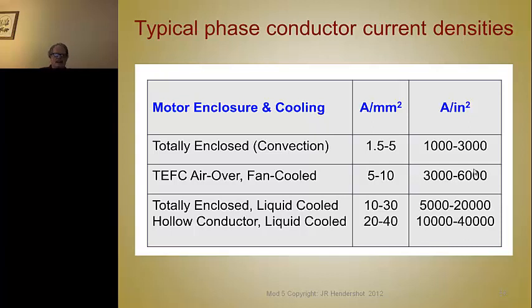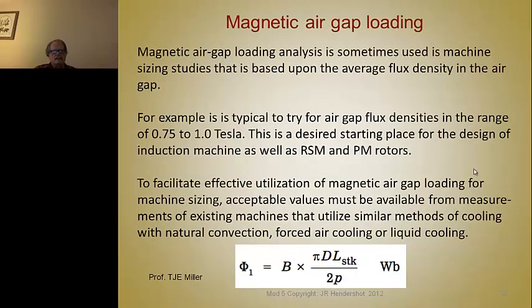If you go much over 5 amps per square millimeter, you need more serious cooling. For magnetic air gap loading, you want to try to have an air gap flux density in the range of 0.75 to 1 Tesla. In a former lecture we assumed that an induction motor is between 0.65 and 0.85, so this is all in the same range. You want to strive for as high as you can — it's pretty tough to get more than 1 Tesla. This is a desired starting point for induction machines as well as reluctance synchronous and PM machines.